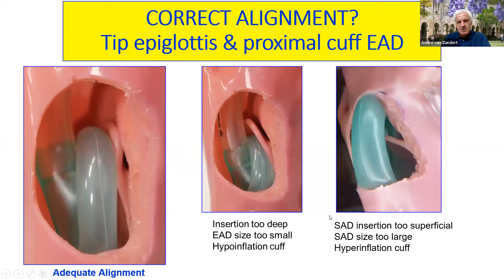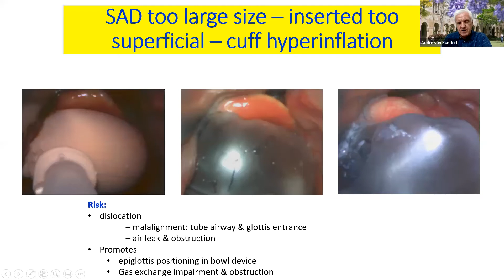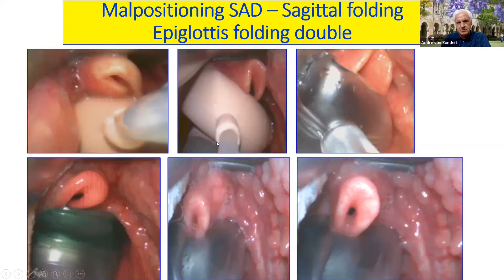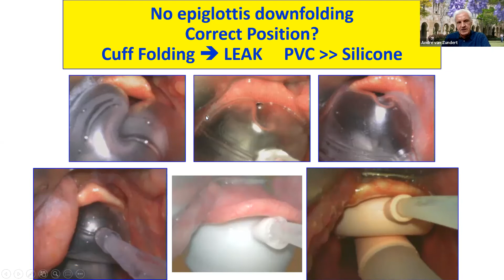Laryngeal masks are very forgiving devices, but the calamity can be dislocation, malalignment. As you can see here, the device is too big. With the airway tube and the glottic entrance malalignment, air leak and obstruction can result, and that promotes epiglottic positioning in the bowl of the device and gas exchange impairment and obstruction. That's not what we want. With epiglottis folding double, you really need to correct this, otherwise you will have obstruction of the airway. Folding, you see with the silicone ones, that is in the correct position. With PVC ones, you see several of these devices were creating leakage.